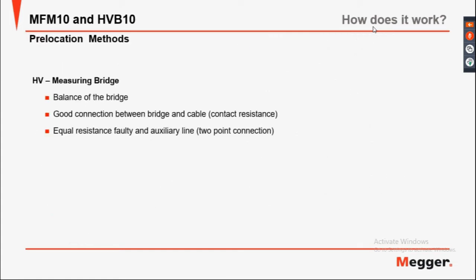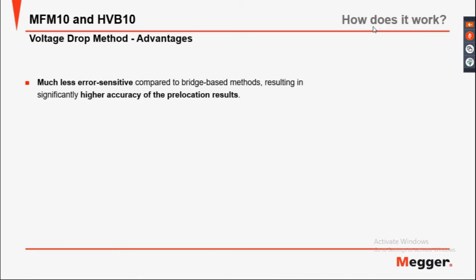Prelocation methods: the high-voltage measuring bridge works by balancing the bridge circuit with good connections between the bridge and cable, and equal resistance in the faulty and auxiliary conductors. The voltage drop method measures both areas of the fault. Advantages of the volt-volt method include being much less error-sensitive compared to bridge-based methods, resulting in significantly higher accuracy for pre-location results.